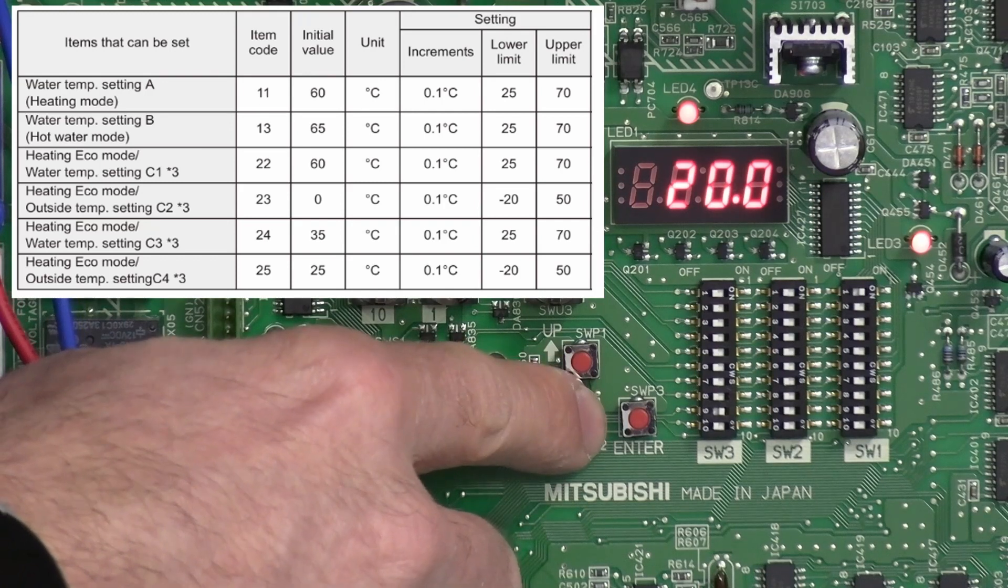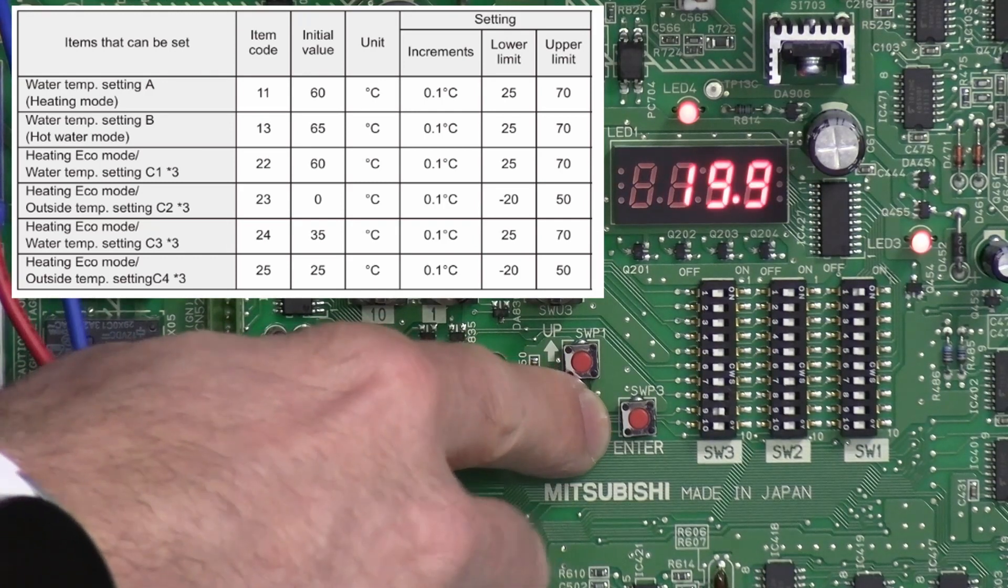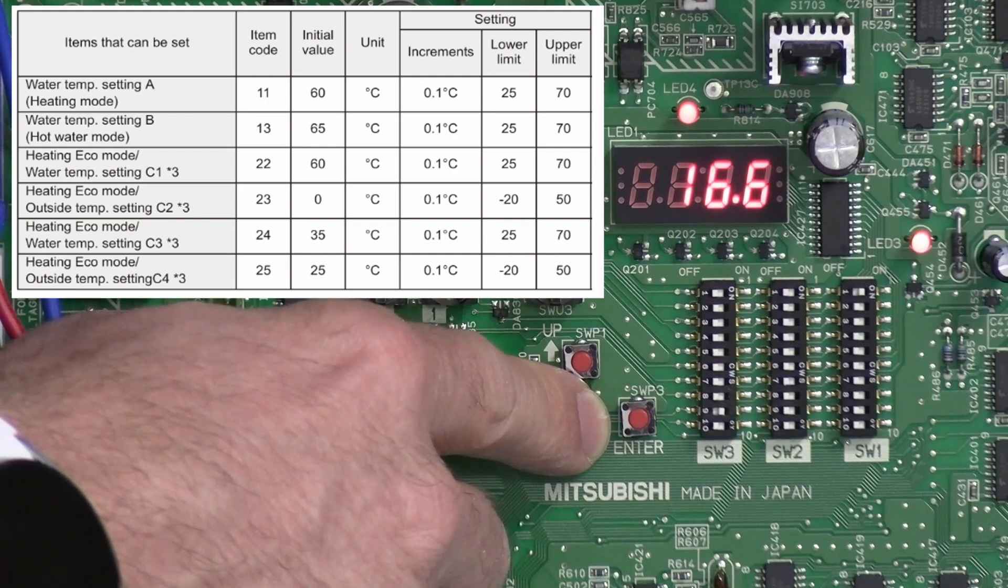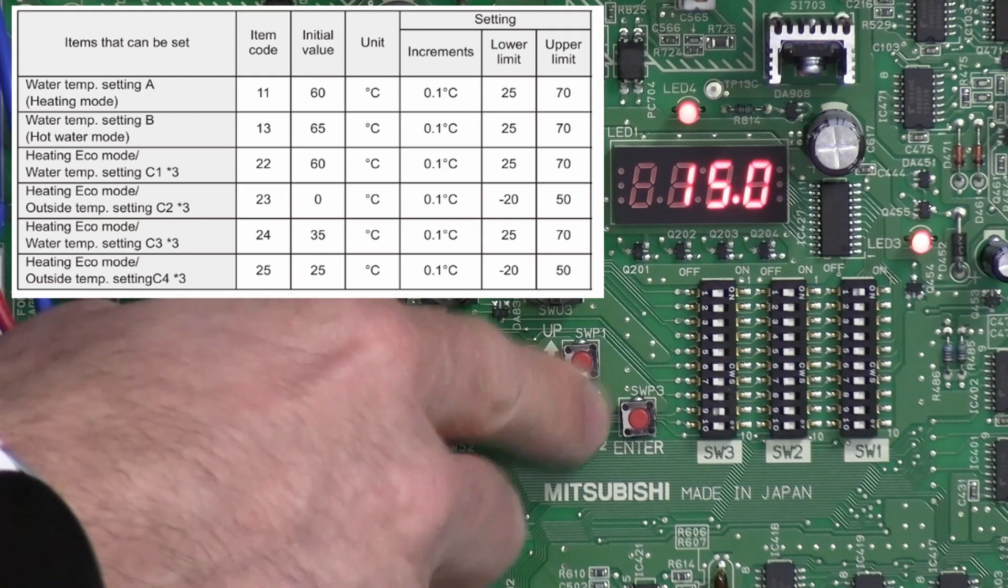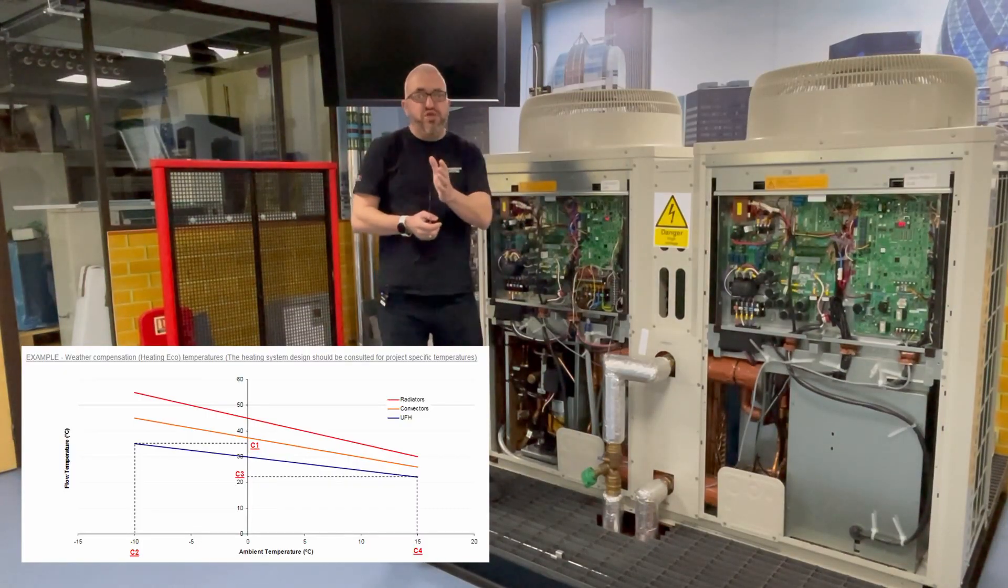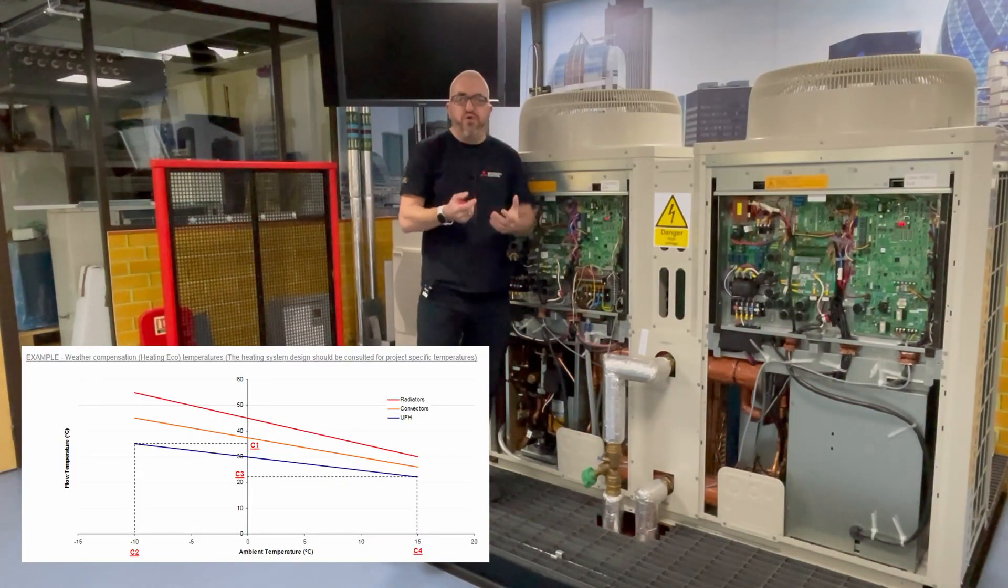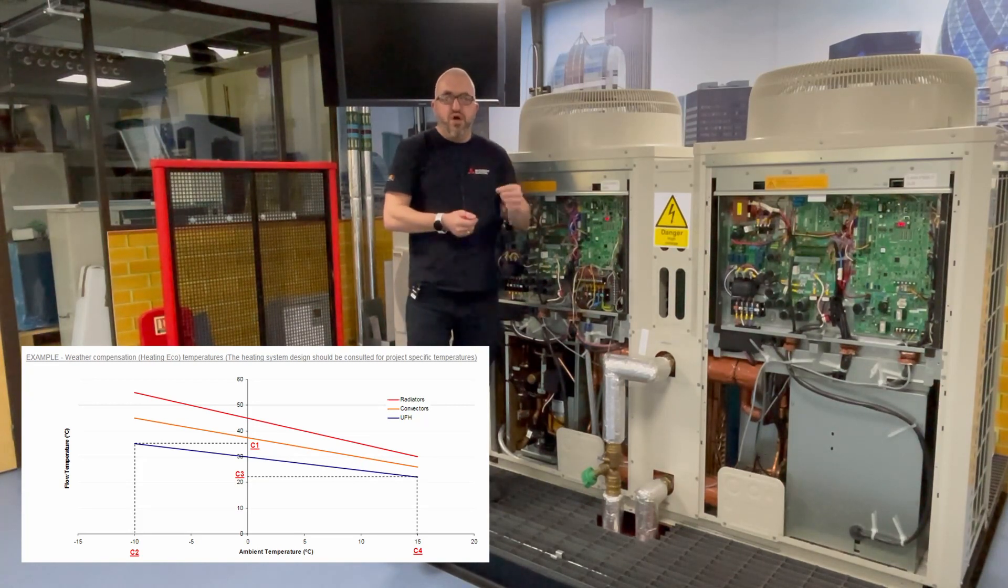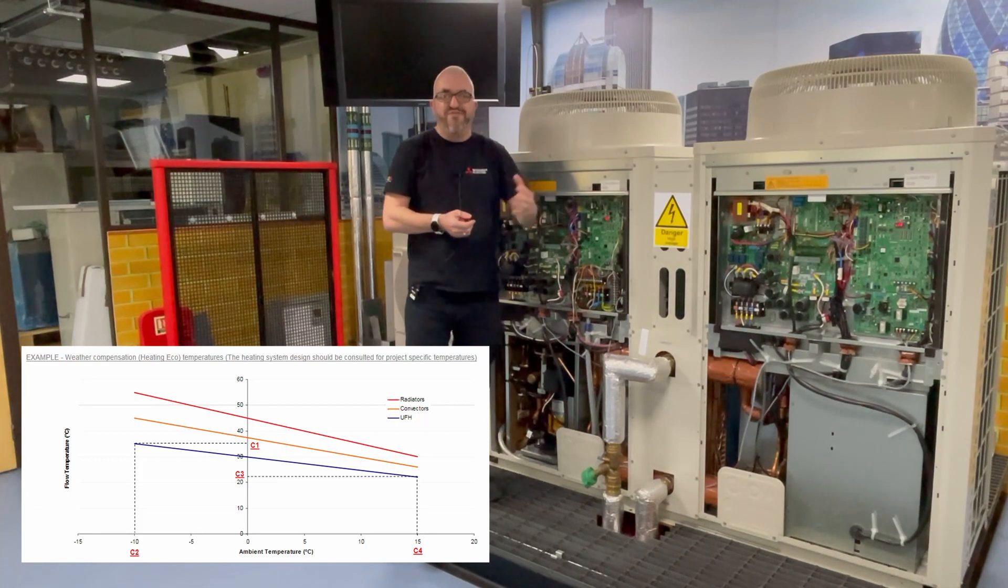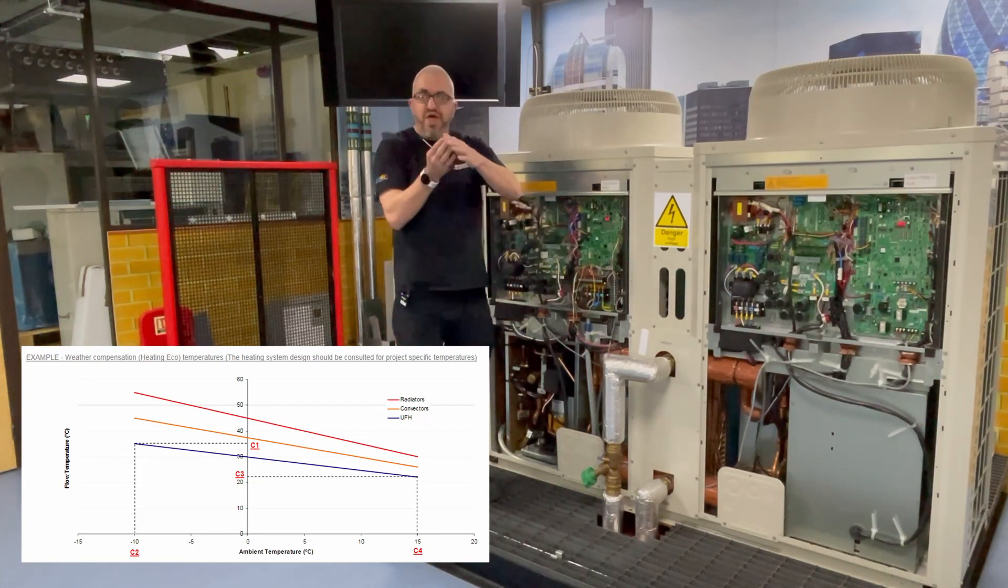And it's currently set to 20 degrees. Let's bring that down a bit, let's say that's maybe 15. Okay, so we say 15 degrees it's going to operate. So 15 degrees or higher it's going to operate at 45 degree flow, or zero degrees or below it's going to operate at 65 degree flow. So that's the linear scale we've set for the target temperature of that water in the system.